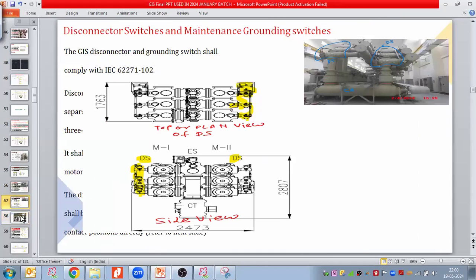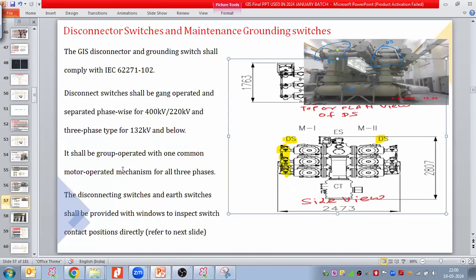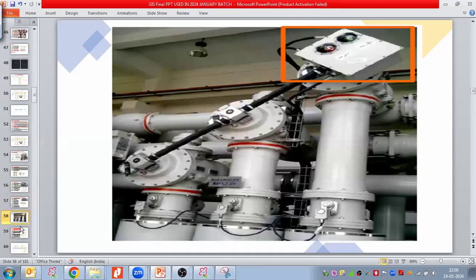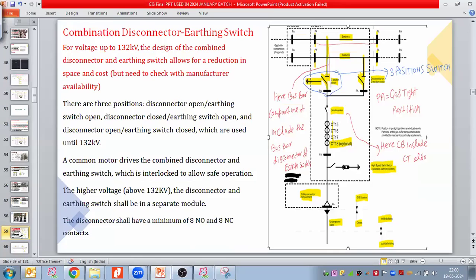Maintenance earthing switch. So here we have the disconnectors module. Now in the disconnectors module, we have two kinds of arrangement with the disconnectors and earthing switch. Up to the 132 kilovolt level, the design of a combined disconnector and earthing switch allows for a reduction in space and a reduction in cost as well.